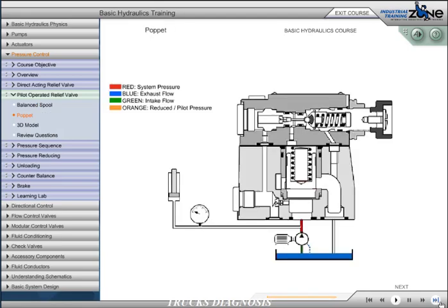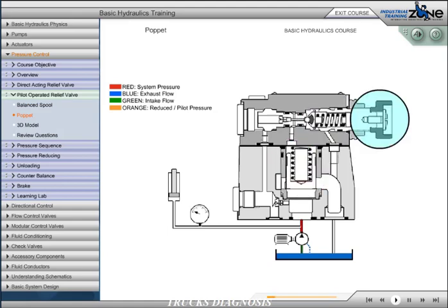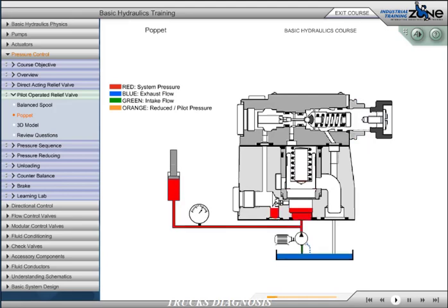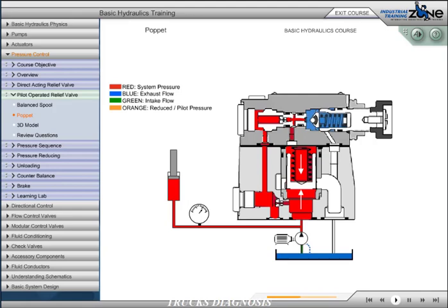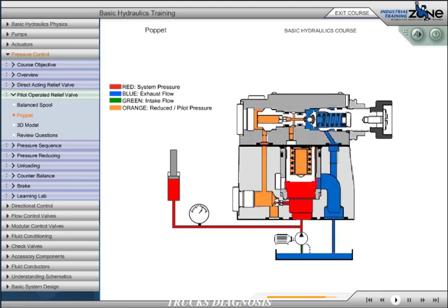The pilot operated pressure relief valve comprises a valve body, a main spool cartridge, and a pilot valve with pressure setting adjustment. Pressure at the primary port acts on the bottom of the main spool, and is simultaneously fed to the spring-loaded side via control lines containing orifices. The pressure is also present at the ball of the pilot valve. If pressure increases above the spring setting of the pilot valve, the ball opens against the spring. Pilot oil on the spring side of the main spool cartridge flows into the spring chamber of the pilot valve and is directed internally to the secondary port and back to tank. Due to the orifices in the control line, a pressure differential exists between the bottom and spring side of the main spool. This pressure differential lifts the main spool off its seat and connects the primary port to the secondary or tank port. Fluid now flows to tank, maintaining the set operating pressure of the valve.